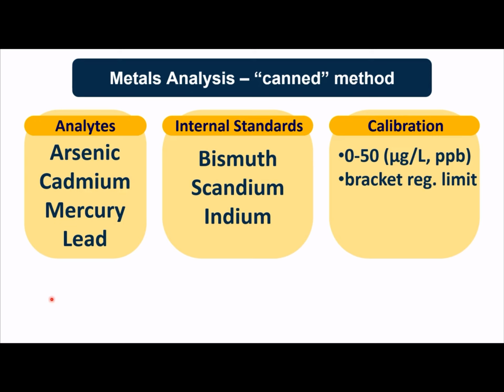So the metals we were testing for listed here: arsenic, cadmium, mercury, lead. The canned method came with these 3 internal standards, and ultimately the calibration ended up being, well, it uses the 0-point metals up to about 50 ppb injection concentration, and not every one of these metals was tested along that range. Everything was really bracketed around the specific regulatory limits of each one of the metals.